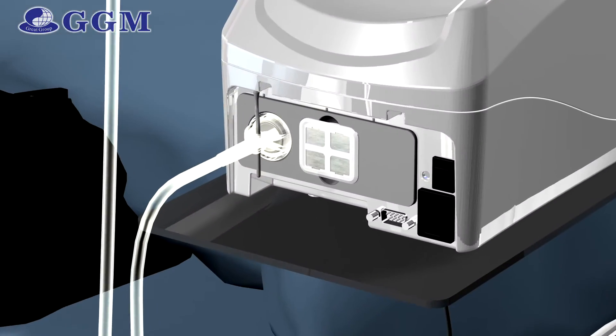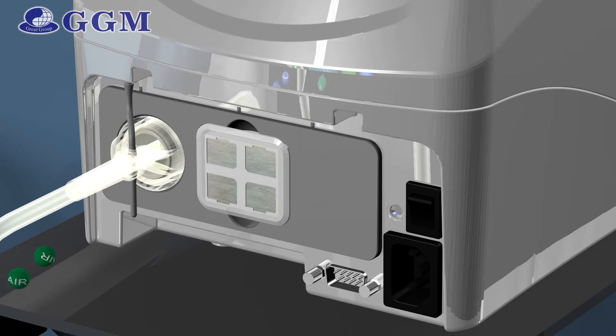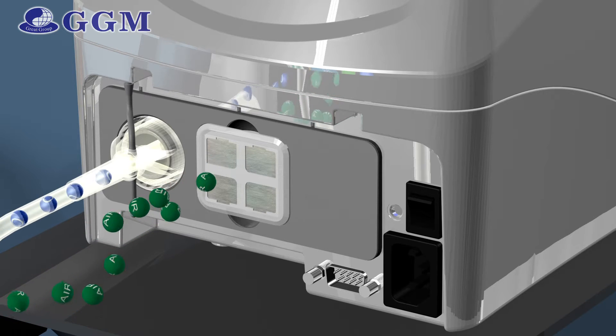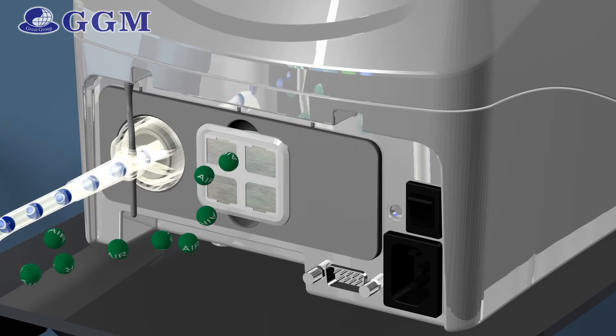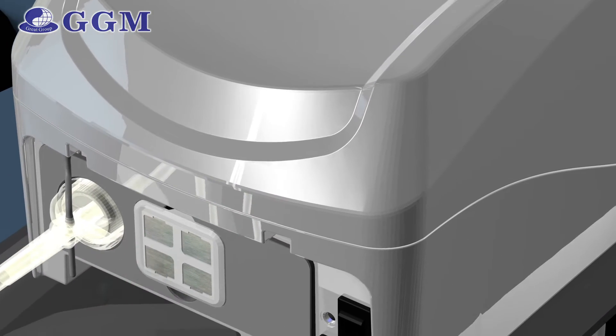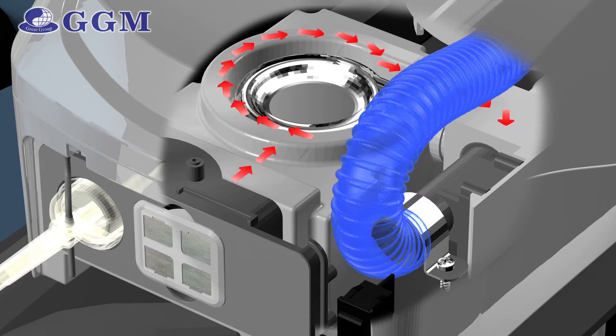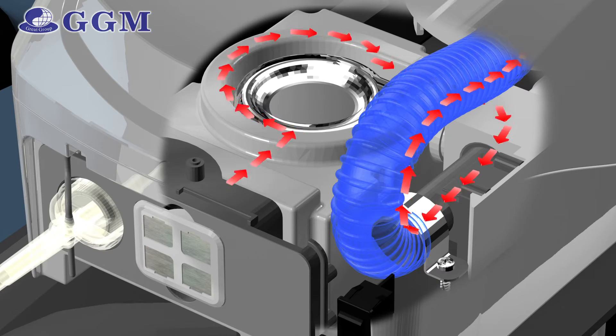Now let's take a look at the technology that makes it possible. Room air and oxygen are collected by a quiet motor through a filtration port. Before entering the flow generator, a blending space is provided to allow oxygen and room air to evenly mix. The flow generator creates flow from 5 to 15 liters per minute for infants and 15 to 50 liters per minute for adults.